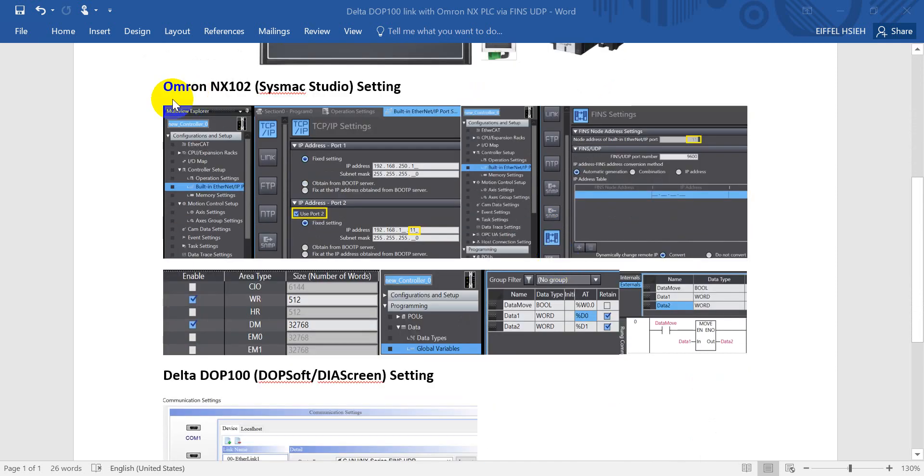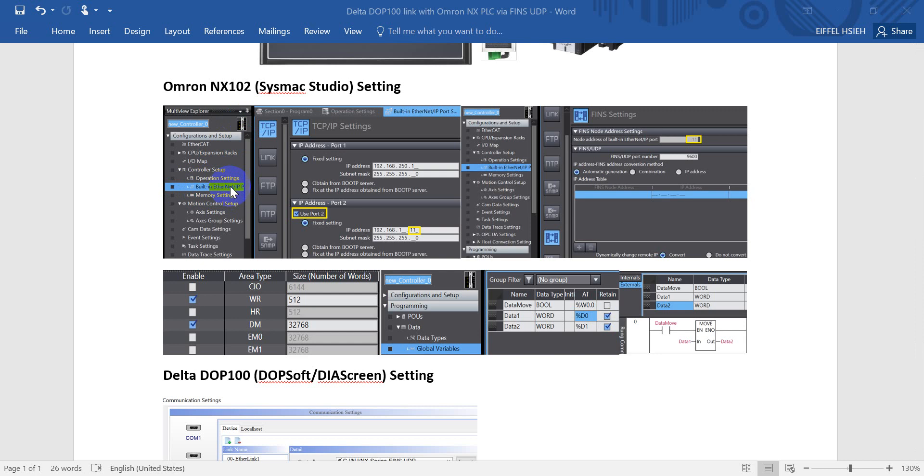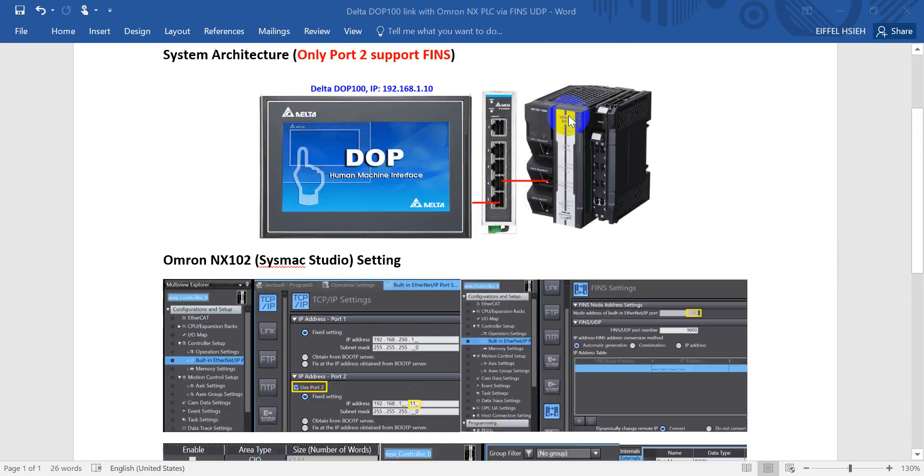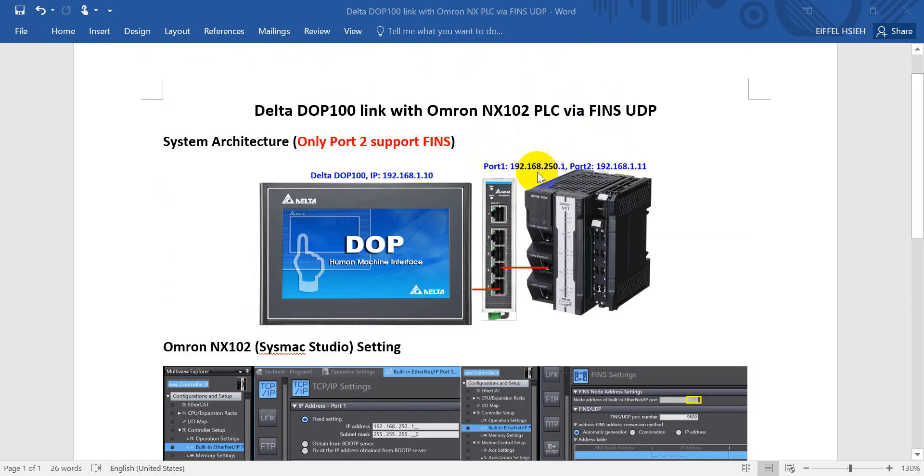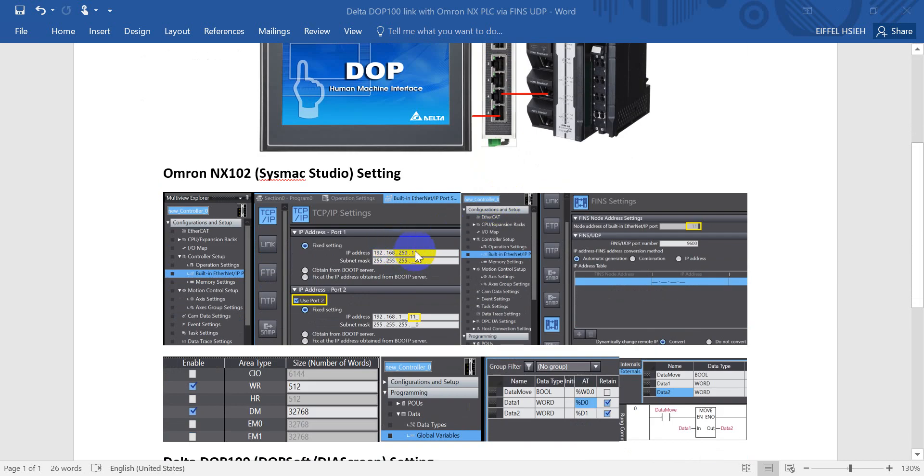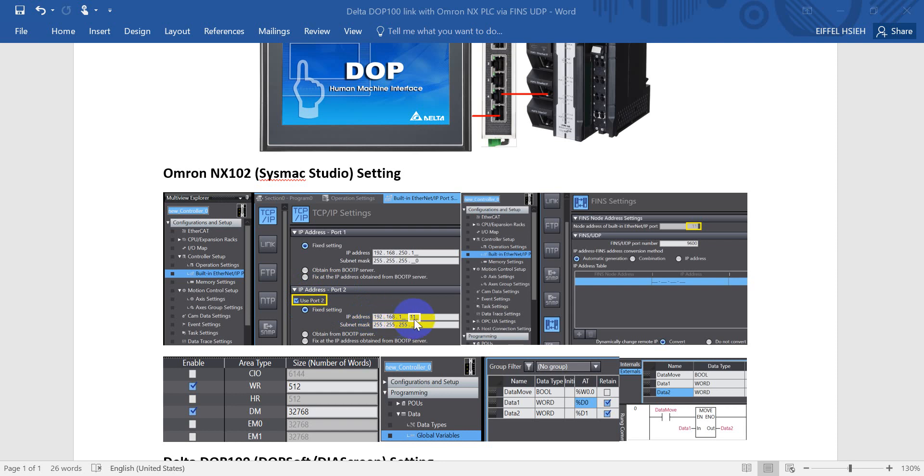Come to OMRON NX102 Sysmac Studio setting. So first of all, we will go to the built-in Ethernet IP setting. As you can see here, we will define the IP address of the first port. Actually this is the default IP address of NX PLC. And then we will define the port 2 with the .1.11. Then select use port 2.